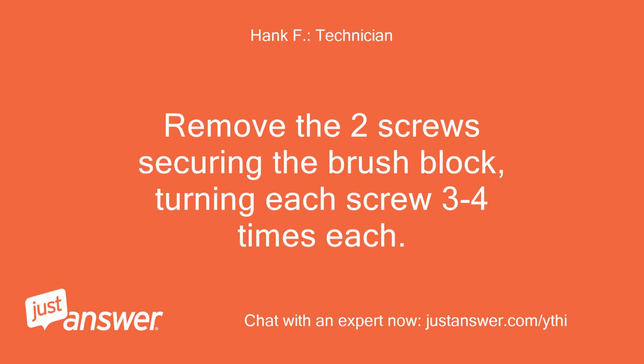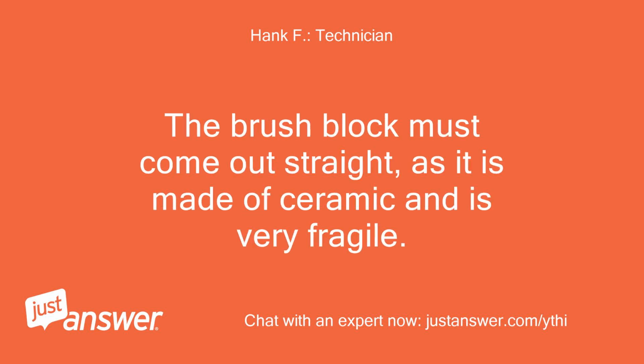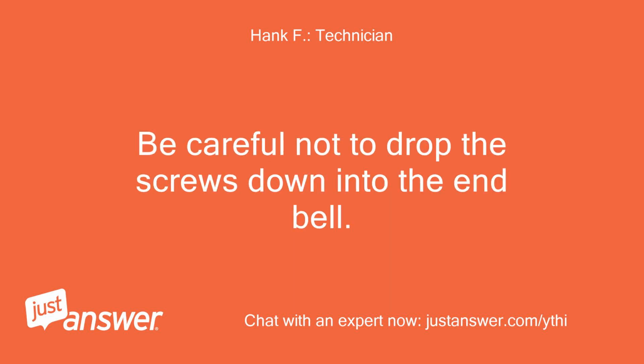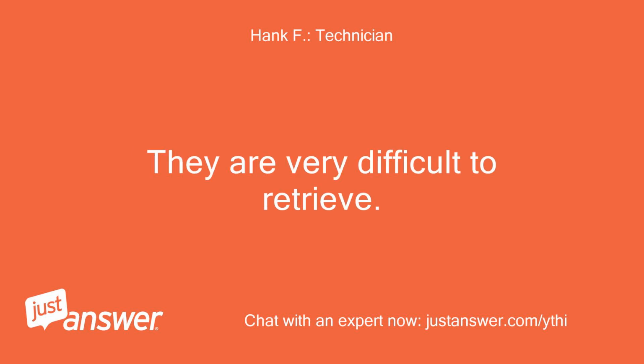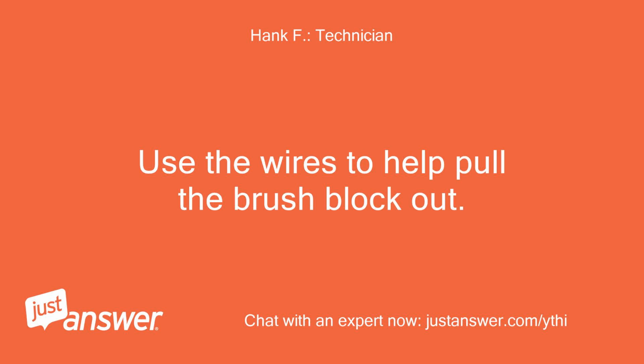Remove the 2 screws securing the brush block, turning each screw 3 to 4 times each. The brush block must come out straight, as it is made of ceramic and is very fragile. Be careful not to drop the screws down into the end bell. They are very difficult to retrieve. Use the wires to help pull the brush block out.